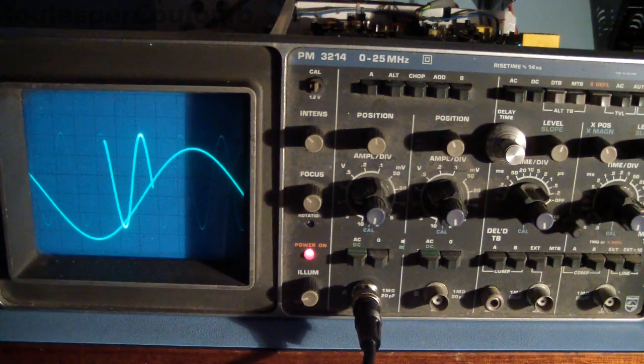Certainly some of the controls are rather dirty and probably need cleaning. Triggering from channel B doesn't seem to work properly. And of course there's that problem with the position control, which I've been very careful with, as that sometimes shorts out the minus 12 volt power supply, which I would think is probably a slightly more serious problem than simply requiring some cleaning. However, I think my next step will be to more or less completely dismantle this instrument, mainly so I can get to the front panel controls and test them and clean all their contacts, etc.